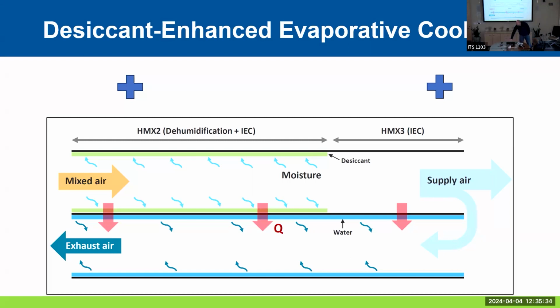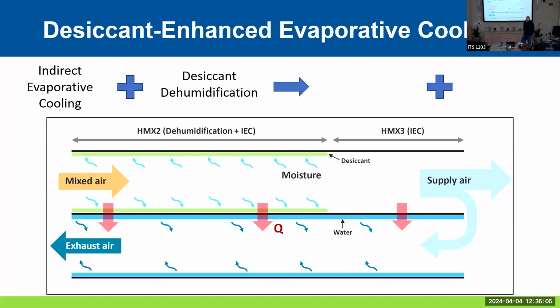More recently, a technology has come around that is an indirect evaporative cooler. What it does is take that cool, wet air and exchange it with hot, dry air, and you get some cool, dry air. That's a very good technology - we've tested it quite a bit at WCEC - but it's still only limited to dry climates to be an effective cooler. So what this technology has done is add desiccant dehumidification.